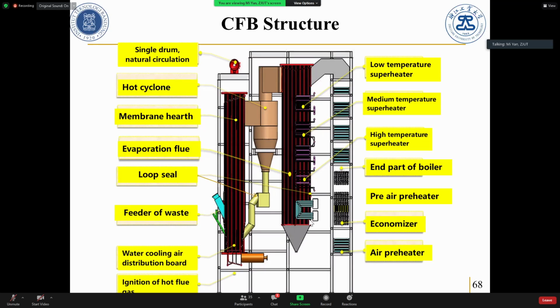And the primary air sits here because we need a high temperature, 350 centigrade, for MSW combustion. For coal combustion, the primary air temperature doesn't necessarily need to be as high, but for MSW we need high primary air temperature to ensure the furnace or combustion temperature is higher, otherwise it's not stable for combustion.